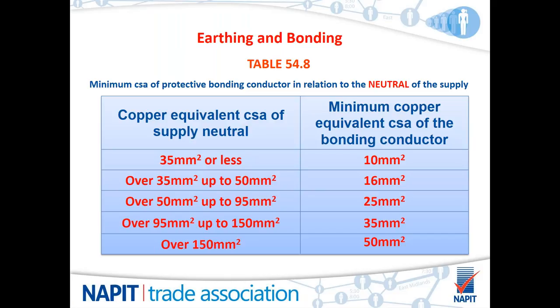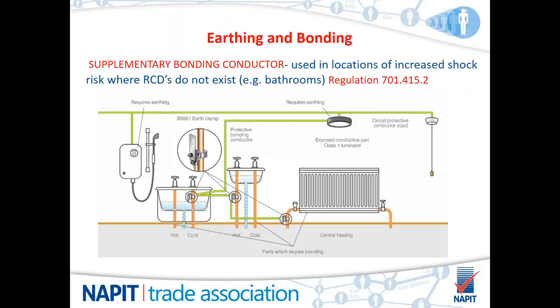And if you were to have a cross-sectional area of 35 mil to 50 mil on the supply neutral, your bonding conductor would jump up to a 16 mil. And as you can see, the higher the cross-sectional area of the supply neutral, the higher the cross-sectional area of the bonding conductor that needs to be installed. Going back to a little bit of terminology and the supplementary bonding conductors, I did mention that they are commonly called cross bonds, as it's easier to say.